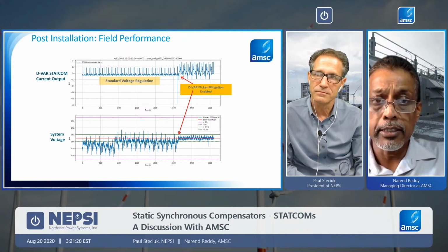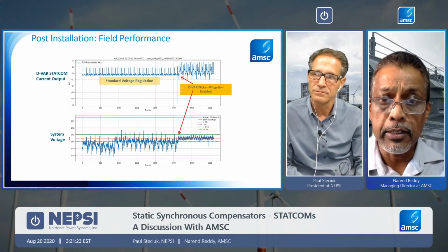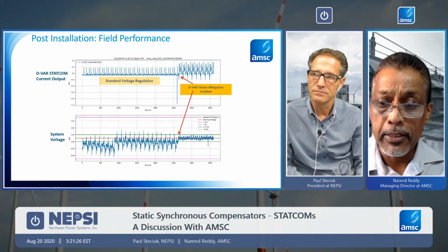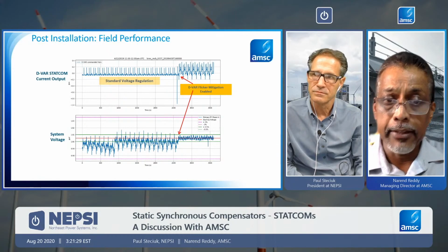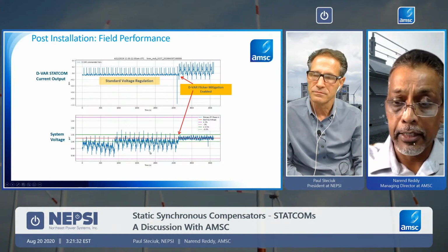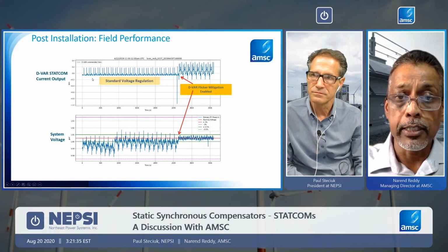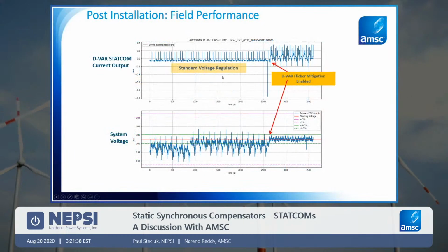Once the system was installed, this is an actual system that's been installed. Here's a recording of the dvar system current and the voltage that it is monitoring at 12.47 kV. In this first phase, the upper graph is the dvar Statcom current output, and here is the voltage. The green line is 1 per unit. The dark green lines are 1.01 and 0.99, so 1% on either side. As you can see, when the system is in standard voltage regulation, the dvar system is responding based on how the voltage is moving, depending on how the operations are going.